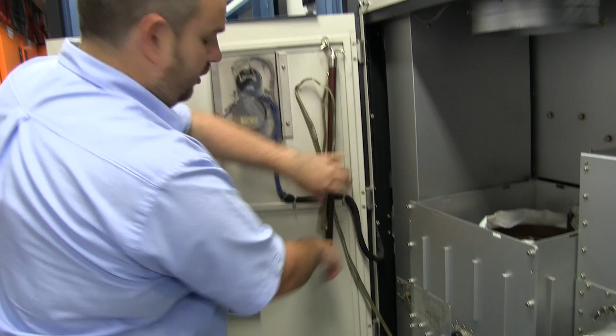There are safety interlocks galore. Because even with that capacitance, you'd get some dielectric absorption and recharging up of that voltage. So there are also other discharging circuits - when you flick off the main switch, that puts a physical contact between the plate voltage and earth, shorting it out and keeping it shorted so the residual charge can't build back up.